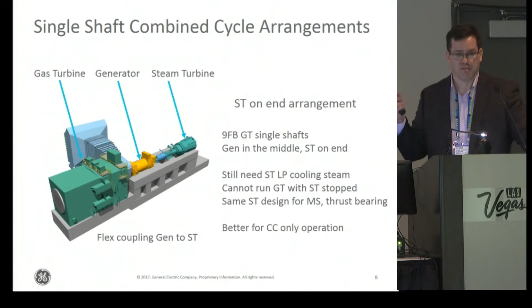So with our latest HA single-shaft combined cycles, we left the generator in the middle, but now we've added a clutch between the steam turbine and the generator. That allows us to start the gas turbine completely independent of the steam turbine. We can still use the generator as a starting means for the gas turbine, but we clutch out the steam turbine and only bring it online later when steam is available from the HRSG. Installing the clutch allowed us to downsize the aux boiler, which helps with air permitting on sites and reduces total capital expenditure.